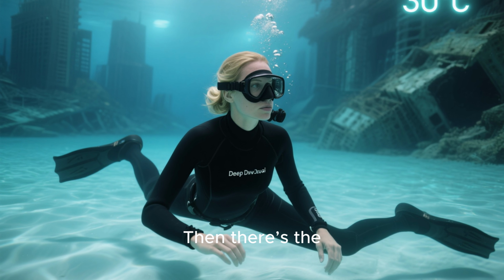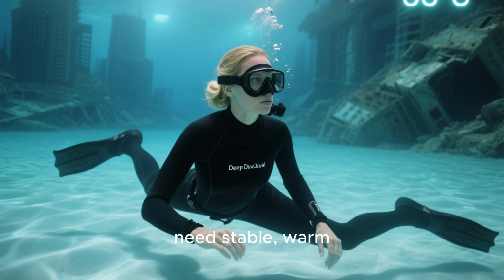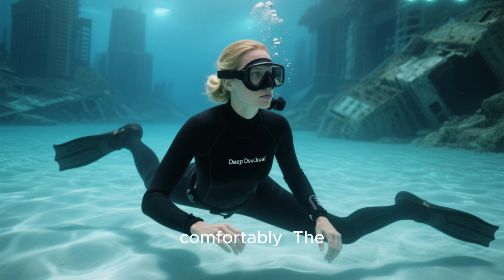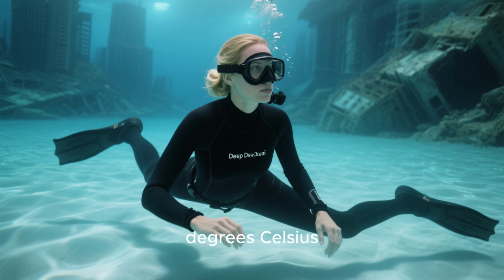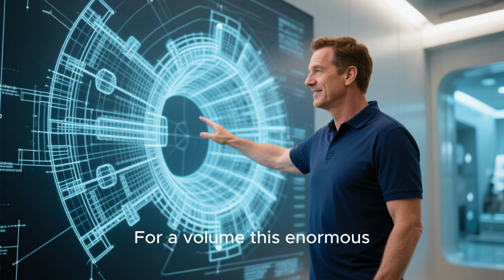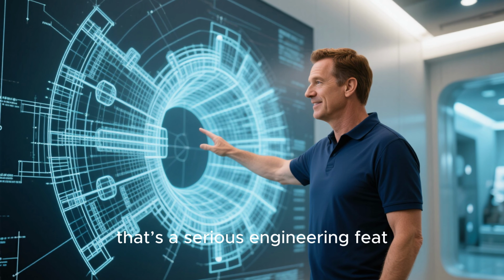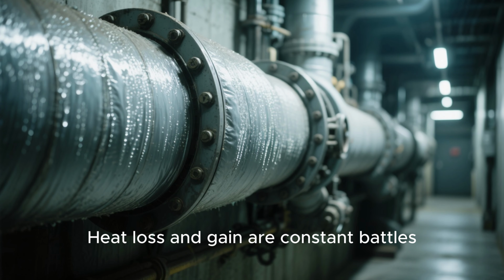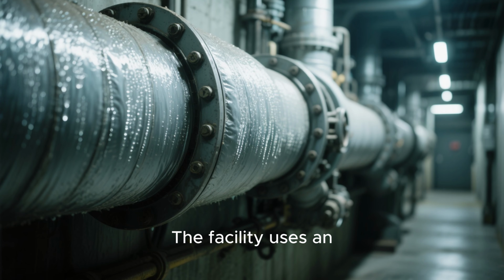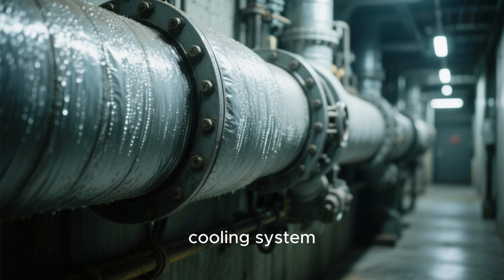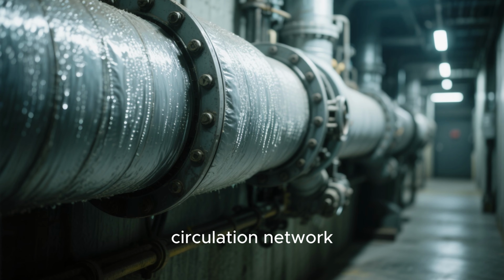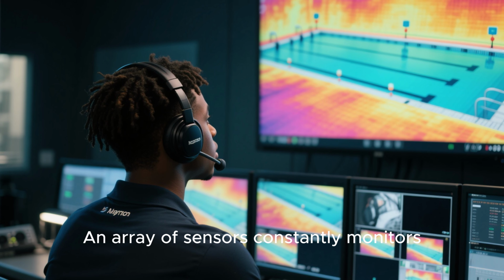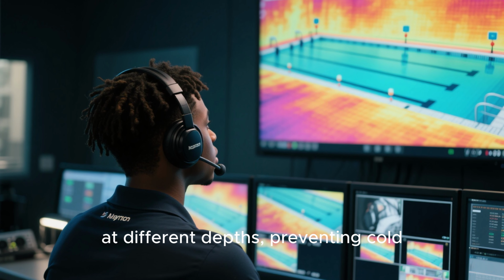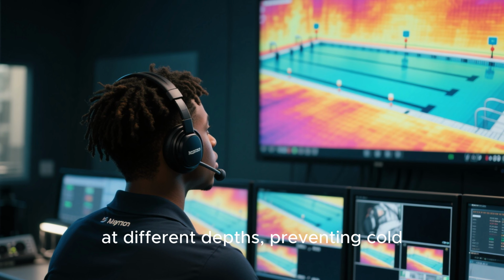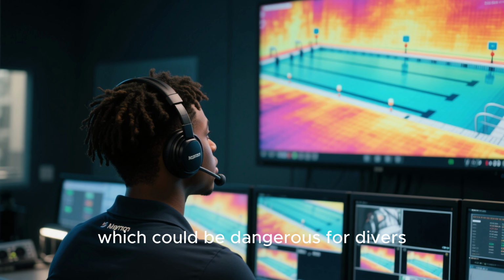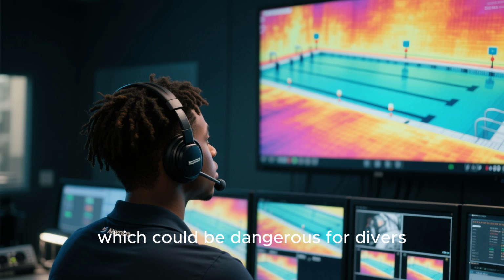Then there's the temperature. Divers need stable, warm water to operate safely and comfortably. The pool is kept at a balmy 30 degrees Celsius. For a volume this enormous, that's a serious engineering feat; heat loss and gain are constant battles. The facility uses an industrial-scale heating and cooling system, fully integrated into the water circulation network. An array of sensors constantly monitors the water temperature at different depths, preventing cold, stratified layers from forming, which could be dangerous for divers.